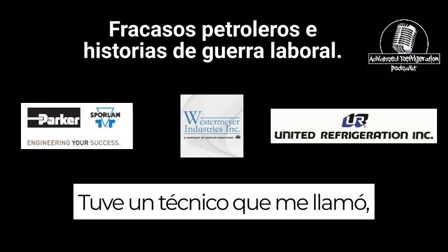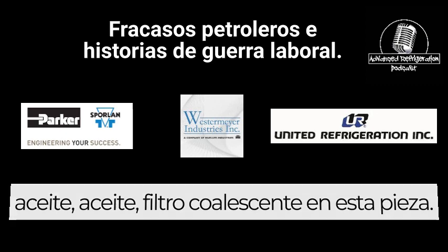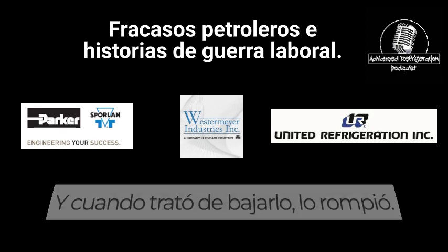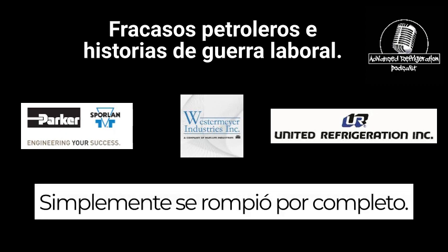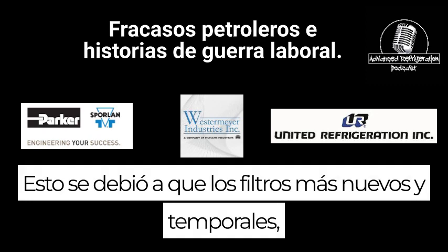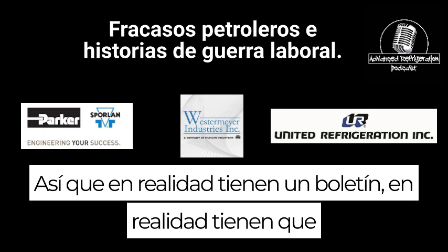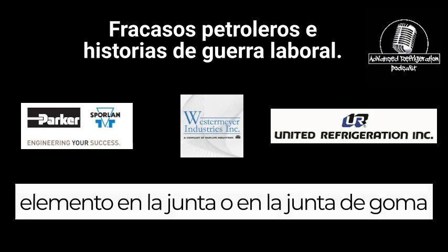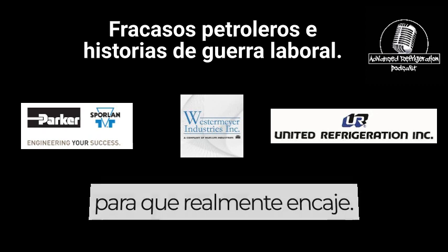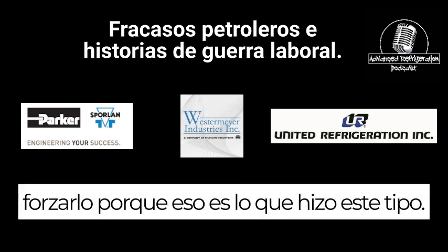I had a technician that called me up freaking out because he's trying to get this oil coalescing filter on this piece. He's like, I can't get it down. And when he tried to get it down, he broke it. It just completely broke off. This was because the newer Temprite filters don't account for that older style. So they actually have a bulletin to make a certain cut in a brand new separator coalescing element in the rubber gasket in order to make it fit. So just be mindful of that so you don't force it down, because that's what this guy did.